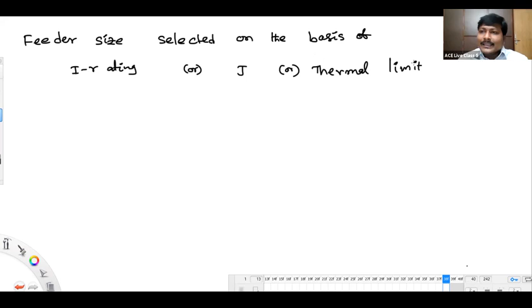Current density, or sometimes you can say it is based on the thermal limit of the conductor. Thermal limit means simply a temperature, or current level, or power, beyond which the conductor may melt down. So who is going to decide the heat in the conductor? Power loss is the term which decides the amount of heat generated. So I square R loss is one of the criteria on the basis of which we decide the feeder conductor size.